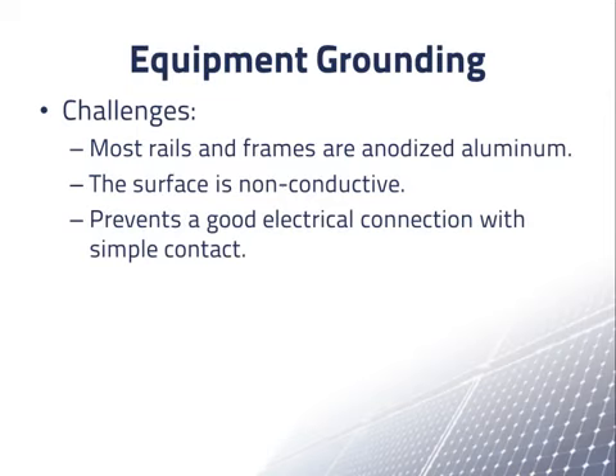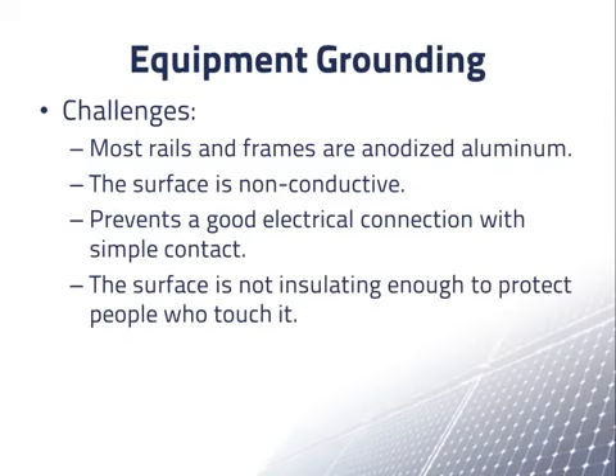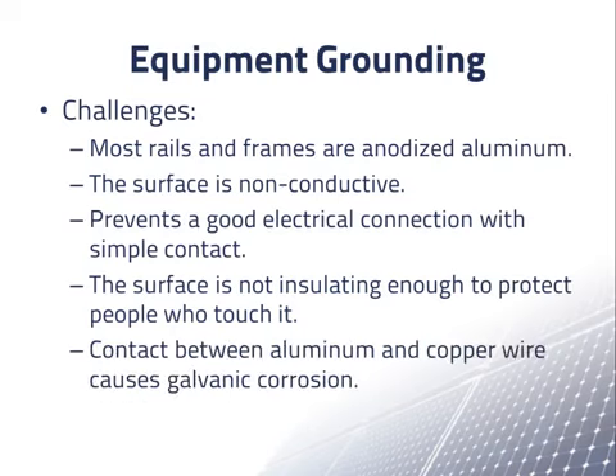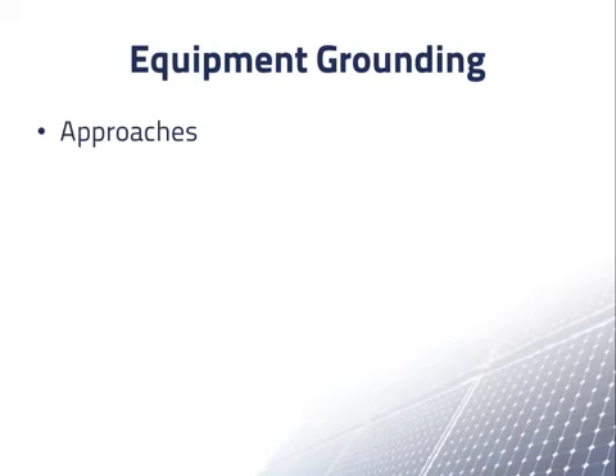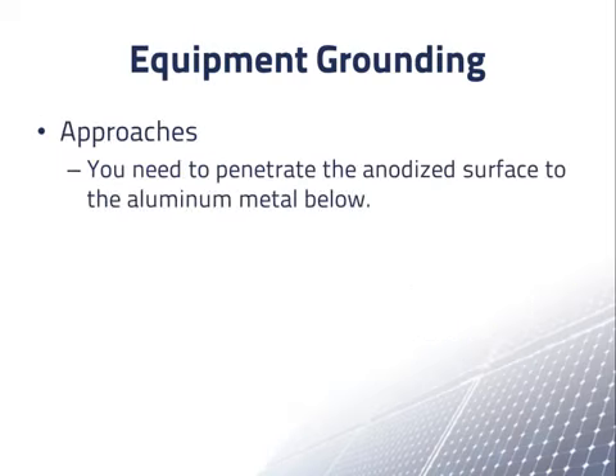However, the surface is not insulating enough to protect someone who touches it from an electrical shock. And in addition, a contact between aluminum and copper wire causes galvanic corrosion, which prevents a good electrical contact. So how do we tackle this problem?